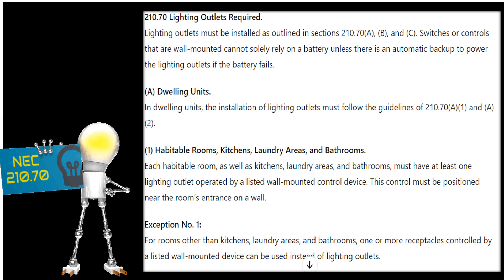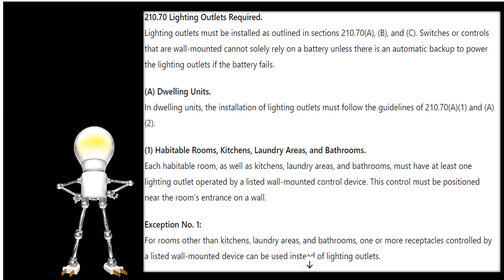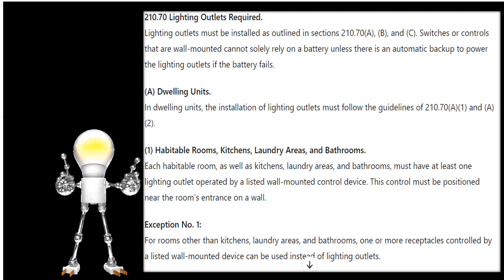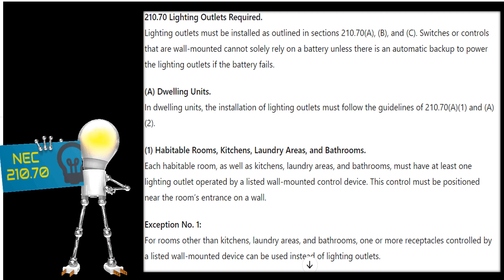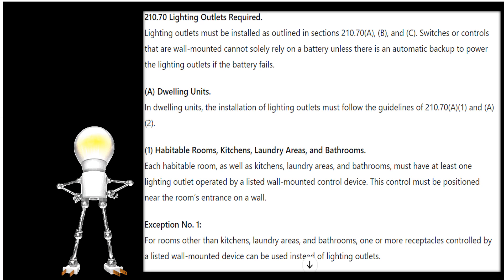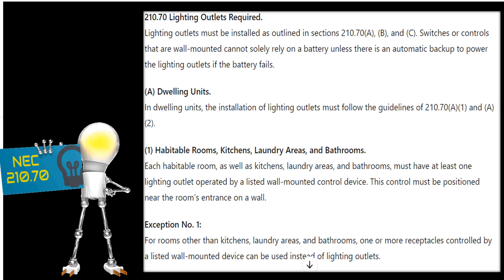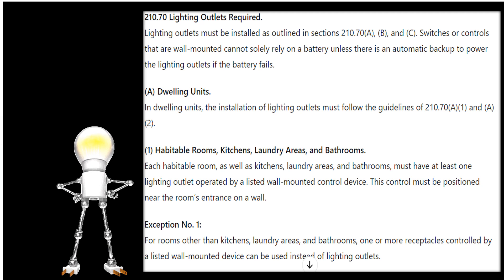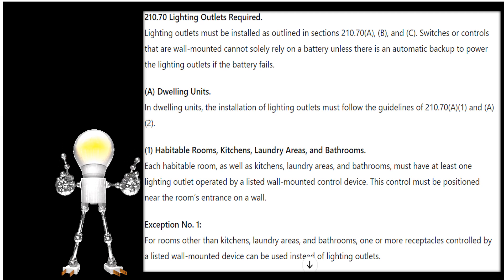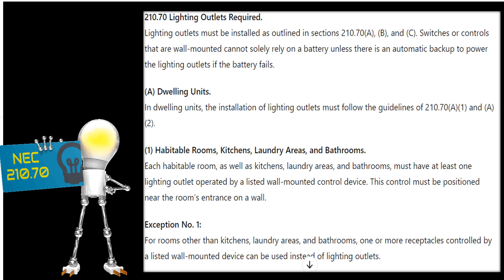What Part 1 is saying is that you have to have lights in habitable rooms, including kitchens, laundry areas, and bathrooms — we have to be able to see in those areas. Remember, a lighting outlet is somewhere that you hang a luminaire. An outlet is where the power comes out. Just because you hang a round box doesn't make it a lighting outlet; the moment you hang a luminaire to it, now it becomes a lighting outlet.